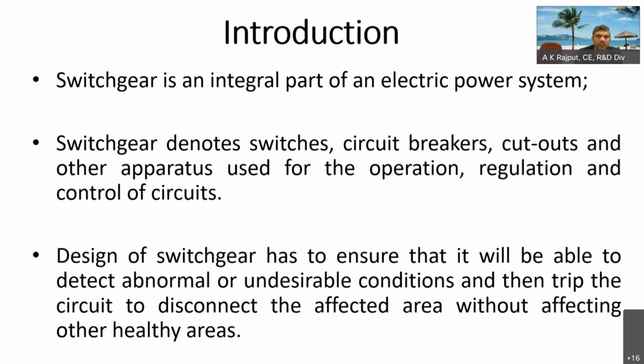We start with the fuses. The journey started with the fuses when the quantum of electricity to be handled was very low, and that worked fine. But as the demand and the requirement increased, many technologies emerged, from oil circuit breakers to now pure air based circuit breakers with regard to environmentally friendly aspects. So the design of the switchgear has to ensure that it will be able to detect abnormal or undesirable conditions in the circuit and then trip the circuit to disconnect the affected area without affecting the other healthy areas. It is basically known as discrimination, and this discriminatory feature is the paramount criterion for the design of the circuit breaker or the switchgear.